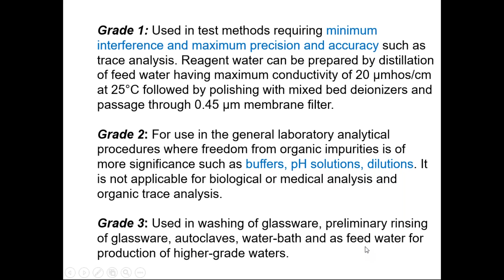This is by the American Society. But here, instead of grade 1, grade 2, and grade 3, you have type 1, type 2, type 3, and type 4. Here, the single asterisk shows that you should filter it through a 0.2 micron membrane filter. Type 2 is prepared by distillation, and type 3 requires the use of a 0.45 micron filter.